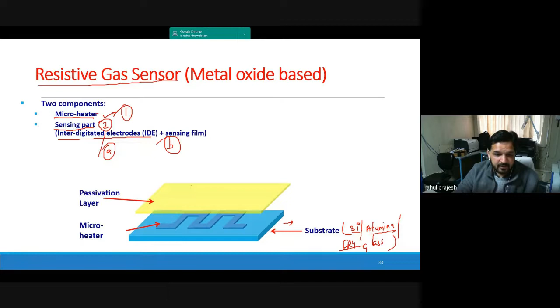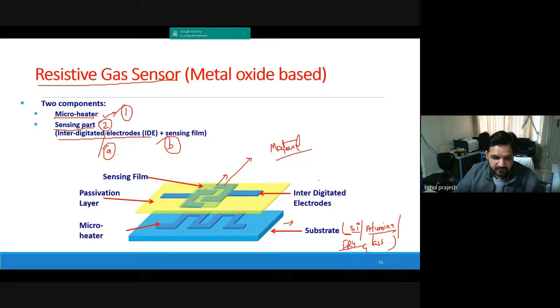Then you have a passivation layer, and then electrodes and sensing film. As I told you, this sensing film is basically a material which changes its resistance when gas is adsorbed on the surface. So gas comes on the surface, and due to that reaction, the resistance changes, and that is measured by the electrodes. But for this reaction to happen, we need a certain temperature, and that temperature is provided by the micro heater.